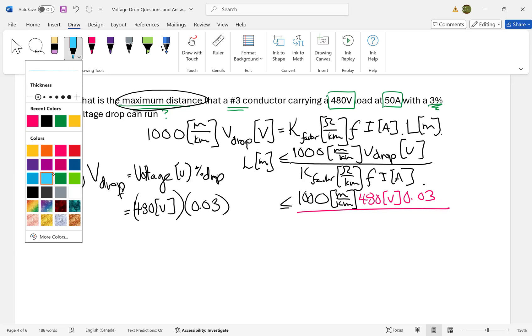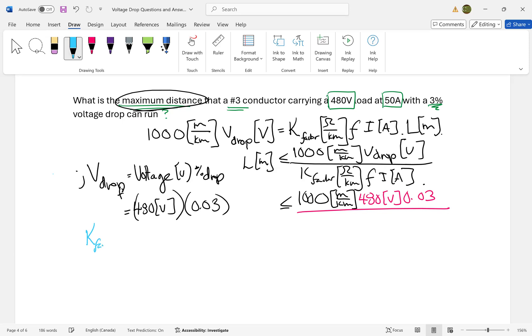I go to Table D3, the voltage drop calculation table. Assuming power factor equals 1, this is copper operating at 75°C. For a #3 conductor, I can read from the chart that K = 0.792 ohms per kilometer.